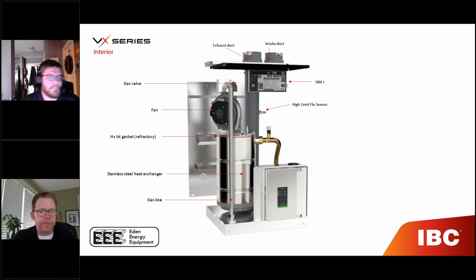Yeah, so the high limit flue sensor is what allows us, working with the Sim Plus module, to use the different UL 636 approved venting materials. It's what allows us to prevent the boiler from ever getting into a lockout situation with your vent material and fully fire that boiler all the way up to 185 Fahrenheit output, our max temperature output, using PVC venting.